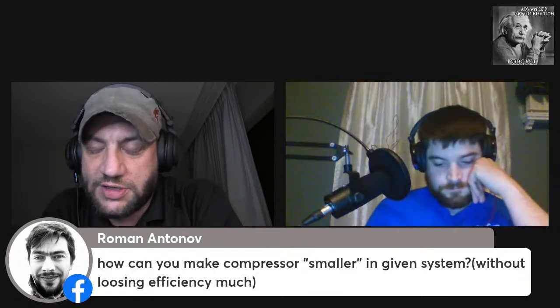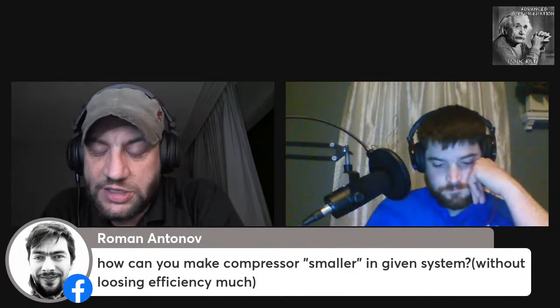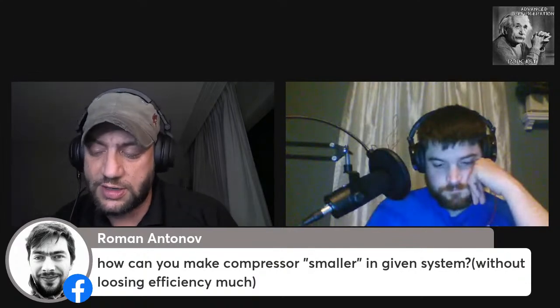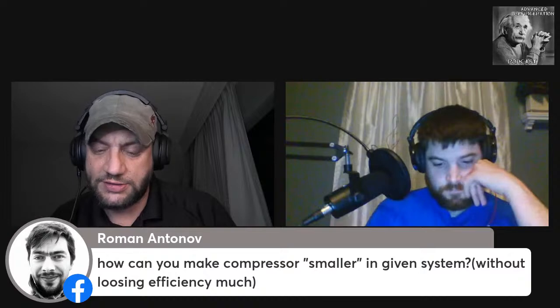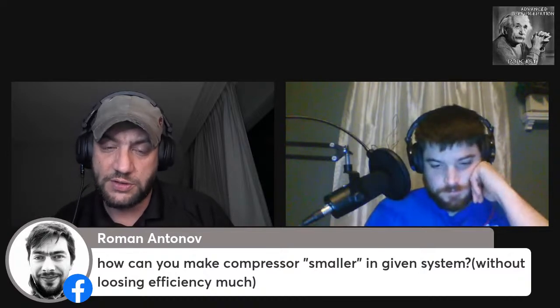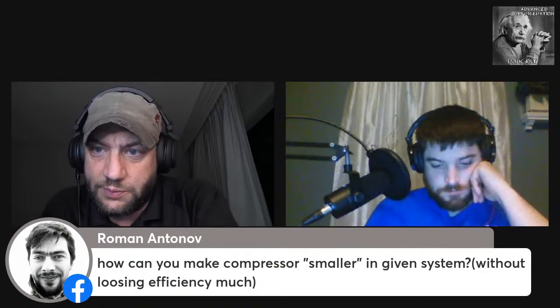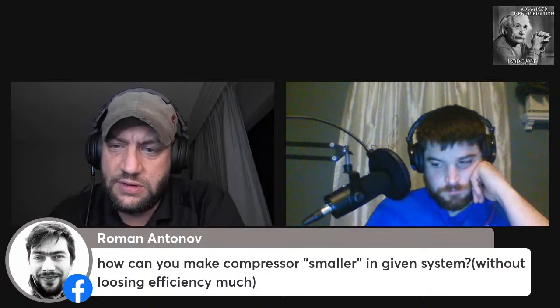Roman, how can I make a compressor smaller in a given system without losing much efficiency? Raise the head pressure. You raise the head pressure and you'll basically downsize that compressor a little bit. If you take the Copeland mobile app and put in any compressor, not the vapor injection stuff, but regular scrolls or regular recips, and you play with the pressures, let's say you're maintaining 20 pounds on the suction and 75 saturated condensing temperature, and then you increase that 75 all the way up to 120, you'll see the capacity drop probably almost 30%, right, Kev? It depends on the compressor, but yeah, it can.